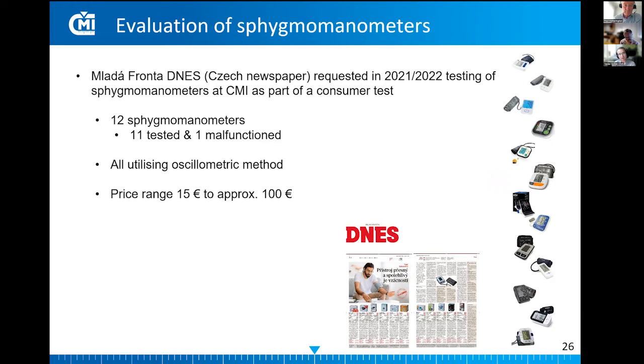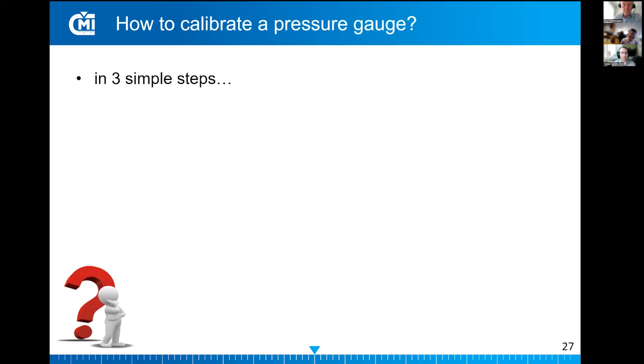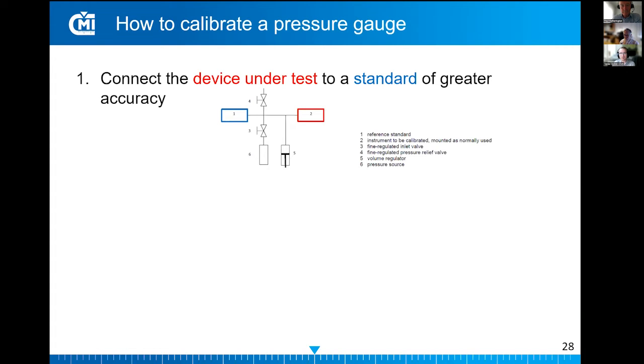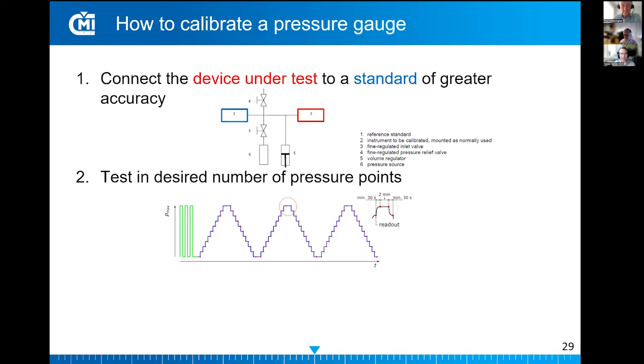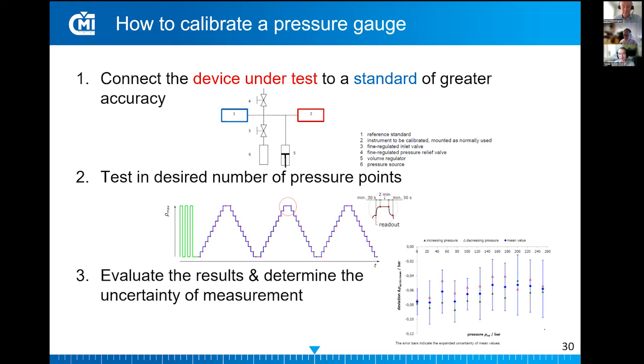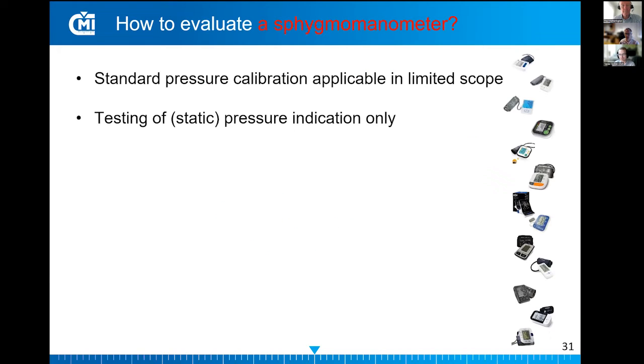Their idea was that it would be something quite simple, like calibrating a pressure gauge, which after some discussion and explanation could theoretically be done in 3 simple steps: connecting the device to a standard of greater accuracy, testing at the desired number of pressure points, and then evaluating the results and determining the uncertainty budget.